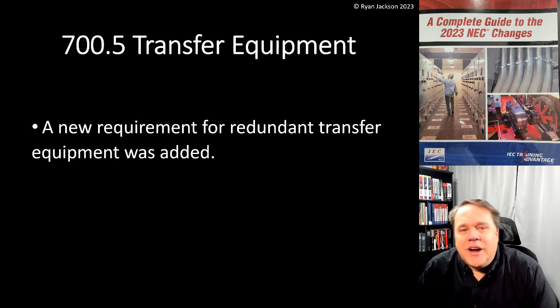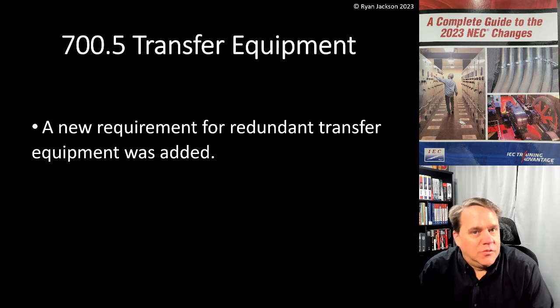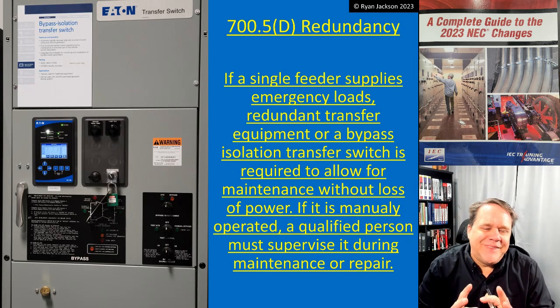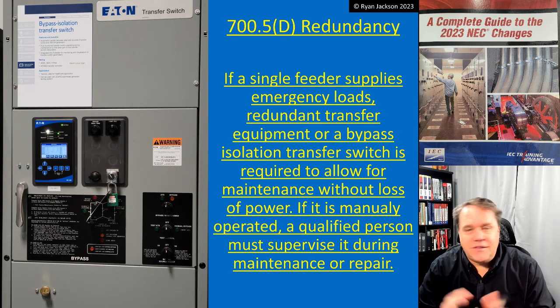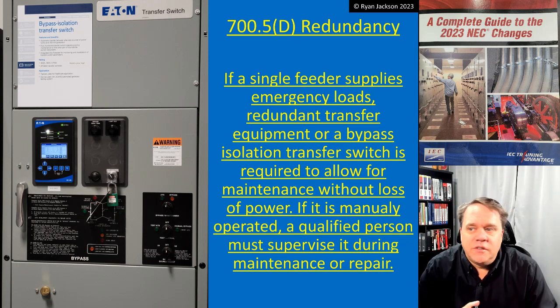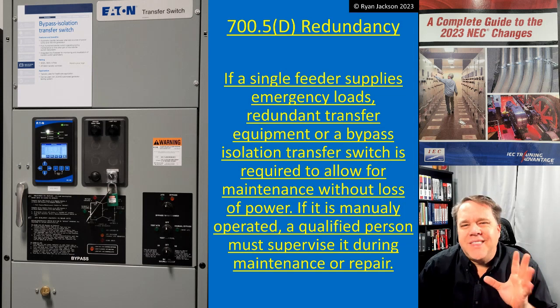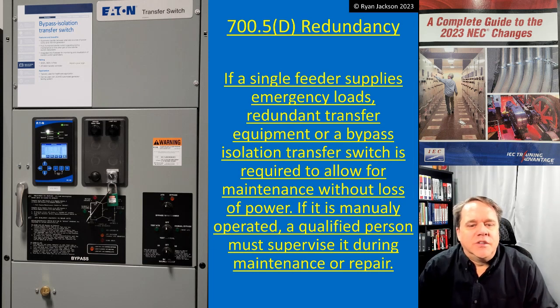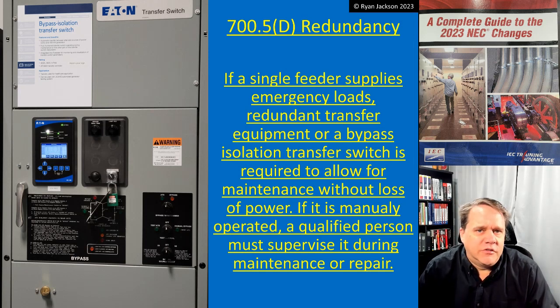700.5 transfer equipment — a new requirement for redundant transfer equipment was added. The code language here isn't perfect, but the idea is pretty clear. If a single feeder supplies emergency loads, then redundant transfer equipment or a bypass isolation transfer switch is required to allow for maintenance without loss of power.